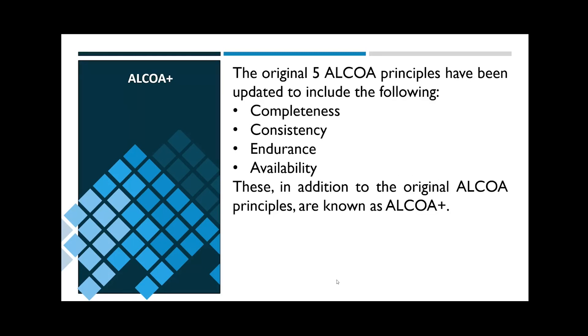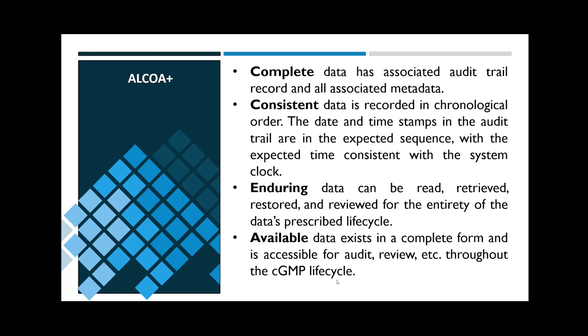Beyond the original ALCOA, there are four more data integrity principles — we call this ALCOA Plus. The four additional principles are completeness, consistency, endurance, and availability. Complete data has all metadata intact and has an associated audit trail record — there are no deletions. Consistent data is recorded in chronological order; all date and time stamps in the audit trail occur in the expected sequence and are consistent with the system clock. Enduring data may be read, retrieved, and reviewed for the entirety of the data's prescribed lifecycle, a period defined by the manufacturer in the SOPs. Available data exists in complete form and is accessible for audit and review throughout the prescribed lifecycle.